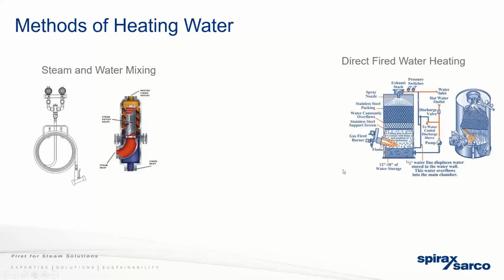Another type of water heater that can be used for washdown is direct fired heaters. In this type of heater, you're using a gas-fired burner, and the flue gases, the exhaust, are heating up the water as it drips down across the flue gases. So you're gaining a lot of the energy from those flue gases that would typically go out of the building to the environment. But the result is you're adding unwanted gases to the water.